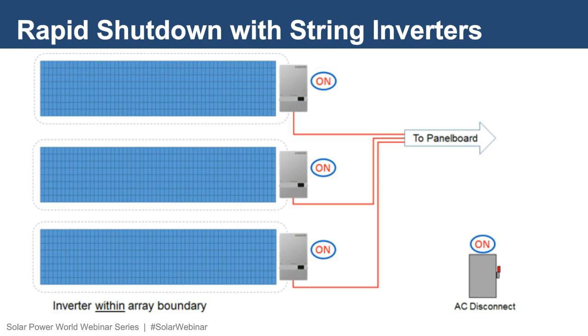Here is an example of a very cost-effective way to meet the array level rapid shutdown requirements of NEC 2014 and 2017. For rooftop installations where the roof is flat and accessible, it may be possible to install the inverters within the array boundary. In this case, the AC conductors leaving the inverter to your building electrical closet are the only conductors subject to the rapid shutdown requirements.